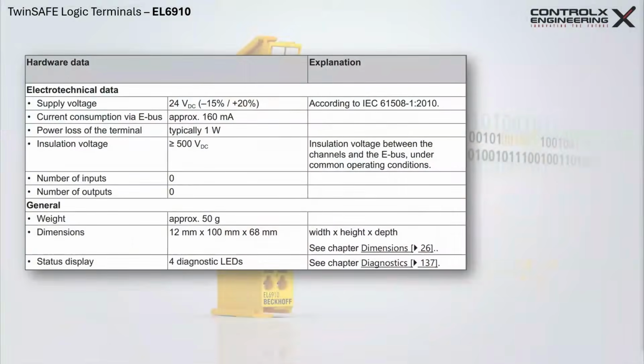Let's review some of the technical specs of the EL6910 logic terminal. It operates on 24 volts and requires approximately 160 mA, which it gets from the eBus. This is a purely logic terminal. It has no local inputs or outputs. There are, however, other combination terminals like the EL1918, which is a logic terminal with 8 safe inputs, or the EL2911, which has 4 safe inputs and 1 safe output. Its physical dimensions are the same as a regular EL terminal and it weighs approximately 50 grams, or 1.8 ounces.